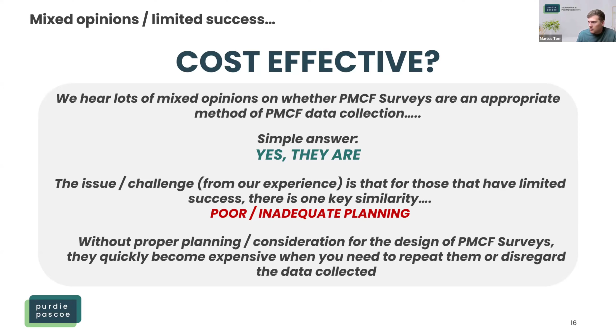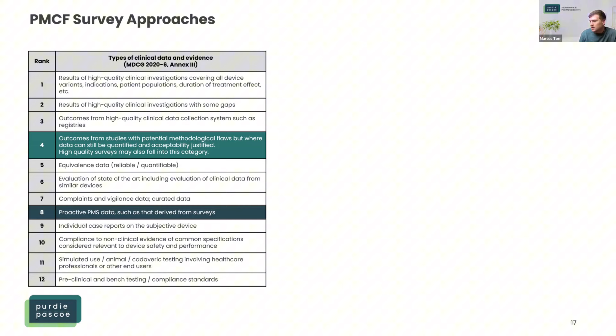So I mentioned the two different survey approaches, and where does this come from? I've got here the table of the clinical data hierarchy from MDCG 2020-6 Annex III. Surveys are mentioned at two of these ranks or levels. Starting with level 4, it states outcomes from studies with potential methodological flaws, but where data can still be quantified and acceptably justified. High quality surveys may fall into this category. The one issue is there's nowhere that actually defines what a high quality survey means, so there's still little guidance out there around that. However, I've got a bit of blurb here on what we see that as meaning, and we'll go into more detail on later slides around what a high quality survey is.